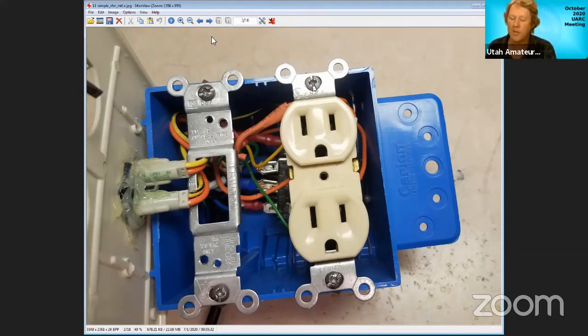At Corinne, where the web SDR site was, for the past couple of years we've been getting approximately 125 volts. It goes up to about 135 volts and down to about 80 volts. So things are constantly going on and off UPSs, and we blew up three UPSs so far. We lost our most recent UPS when the line voltage was probably around 160 volts for hours at a time.